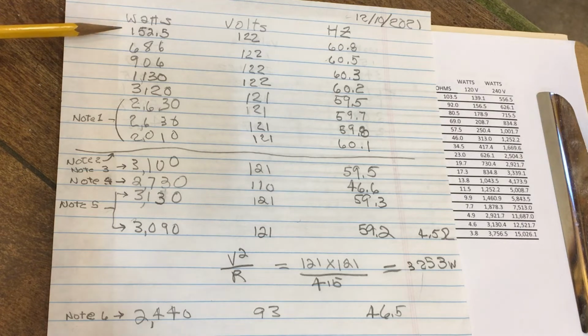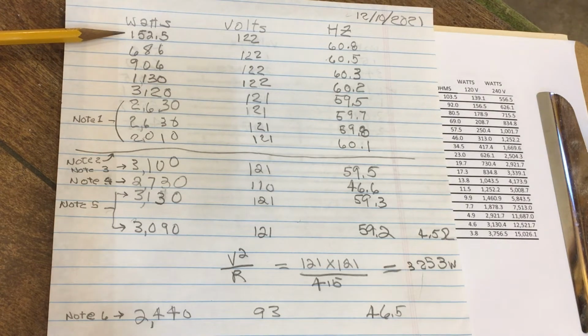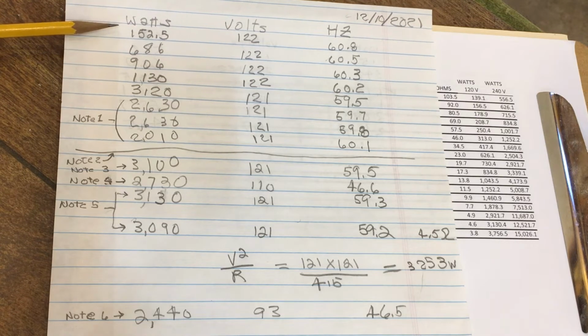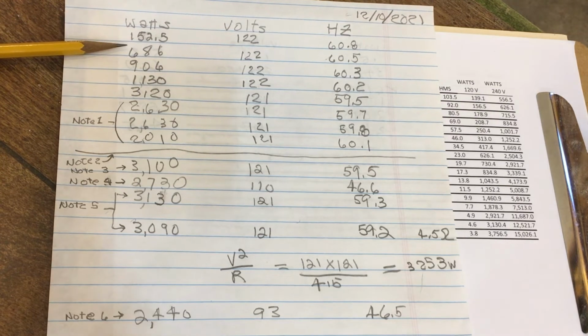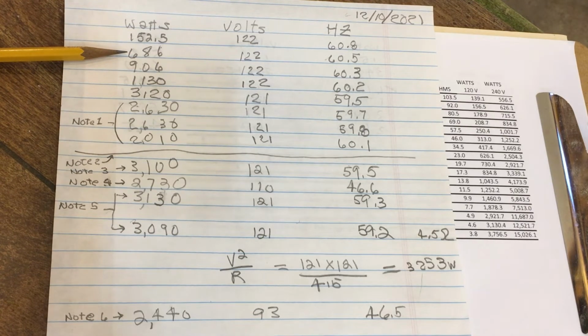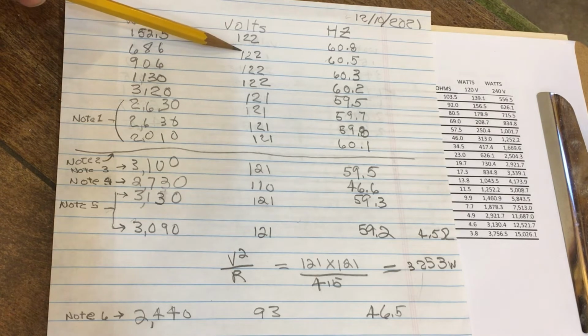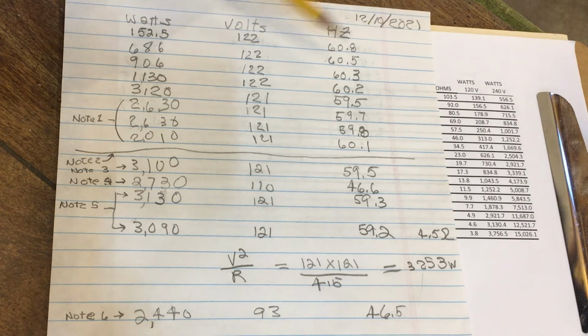The first load that was applied produced an output wattage of 152.5 watts, and basically that's a situation where all 9 of the heating elements are hooked up in series. Then as I flipped the toggle switches, the heating elements were hooked up in parallel or series to change the loading on the generator. The next one I switched so the load went up to 686, and as you see the voltage is 122, very, very commendable, 60.5 hertz.